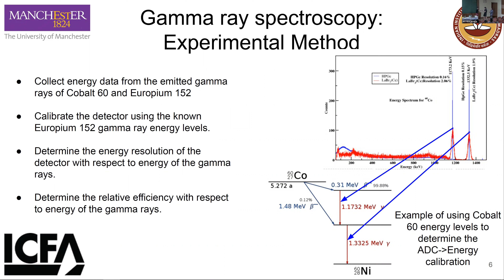Okay, so as John mentioned briefly before, for calibration we take these known gamma peaks, as written here, with their energies in kiloelectron volts. What we do, for most parts of the experiment, is select each peak and put a Gaussian over it, then take various parameters of the Gaussian, which we will use now. The first thing we did was calibrate the detector using the europium-152 source. Like I said, a Gaussian is fitted to each peak, and in this one we took the mean of each peak, where the mean would be the channel number. And then we fitted using this equation here, where E is the energy, x is the channel number, and a, b, and c are constants. As you can see here, the quadratic term is actually very small. This exists because at higher energies, it does take a quadratic shape.